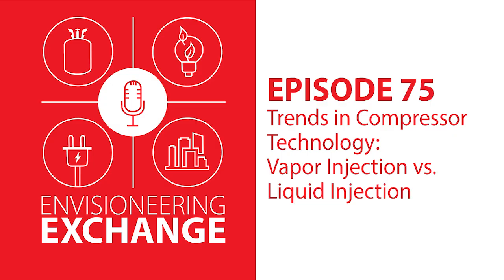Exactly. Yeah. You definitely need a bit more feedback there than just a standard valve driver. In this case, it's really suited for electronic valves more so than a mechanical TXV, just because you need that quick real-time feedback that you get with an electronic valve that you don't necessarily have with a standard thermostatic valve. Now, what about putting a TXV on the main evaporator? Is that still doable? Yeah, it's still okay.